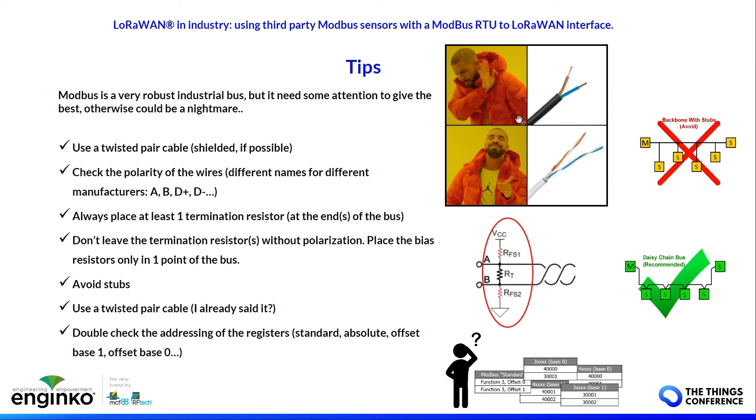Avoid stubs — connect devices as a daisy-chain bus without stubs. Use twisted pair cable. Double-check the addressing of registers: be aware of the standard absolute offset, base-one, and base-zero addressing differences. These are the main issues you can encounter when using a Modbus master.